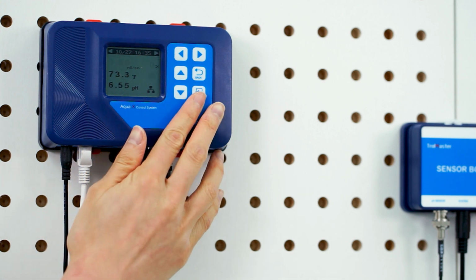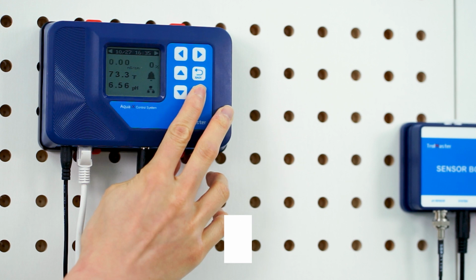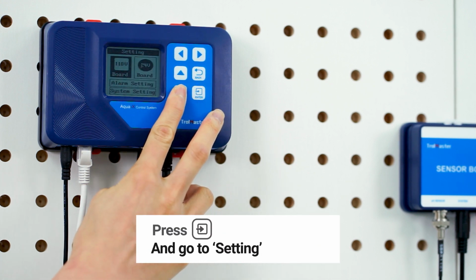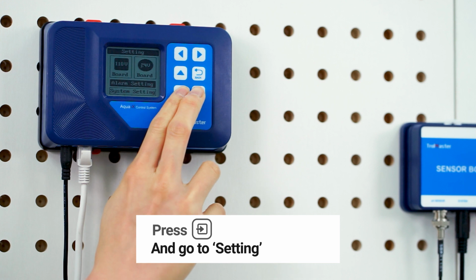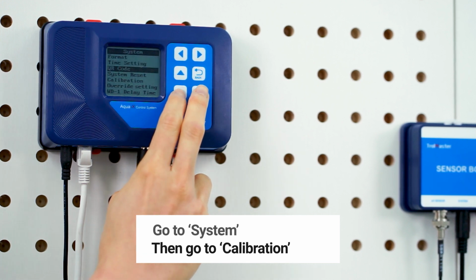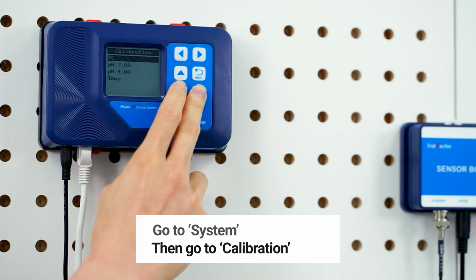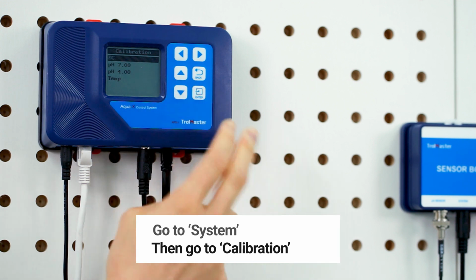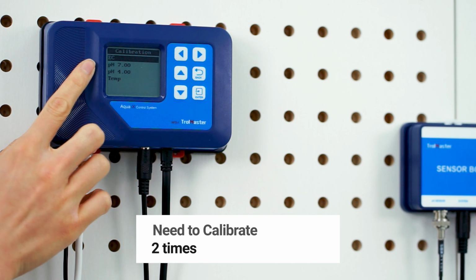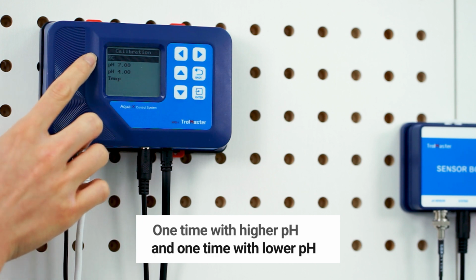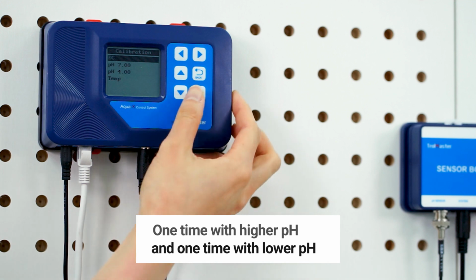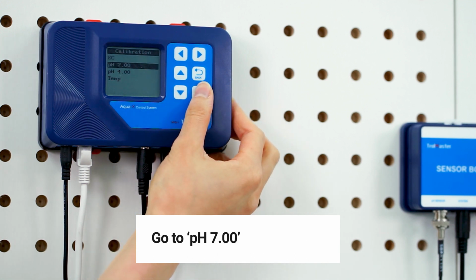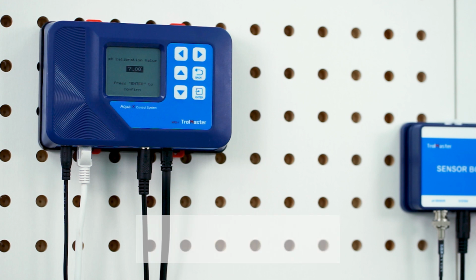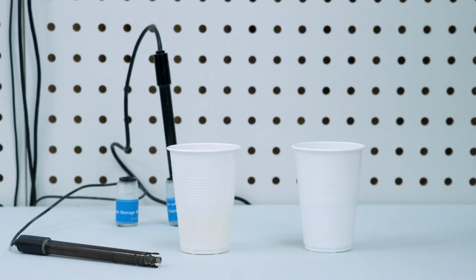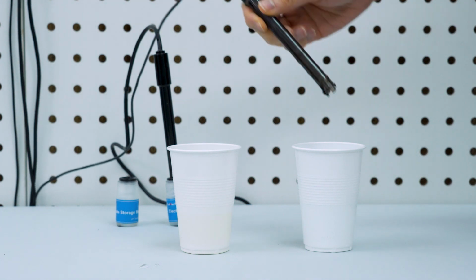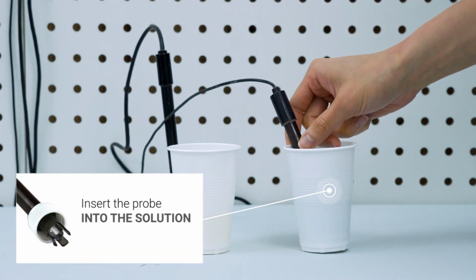On the main menu of the Aqua-X controller, press the Enter button. Go to Calibration. You'll need to calibrate it 2 times. One time with higher pH and one time lower. We'll start with a pH 7. Be sure to insert the pH probe into the solution before calibrating.